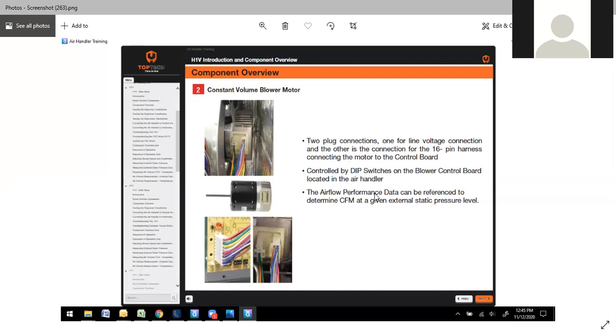Controlled by dip switches on the blower control board located in the air handler. The airflow performance data can be referenced to determine the CFM at a given external static pressure. That's very important. Just because you think that you have it set to a certain speed, if you don't know your static pressure, you just have it set at a certain range. You don't really know what you're putting out unless you, number one, check your static pressure, or number two, do the airflow calculation. At that point, you can know exactly what you're putting out.